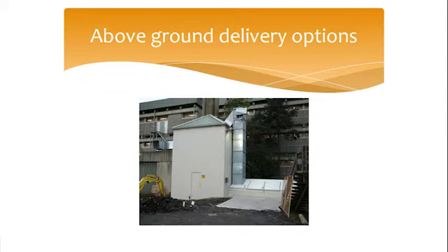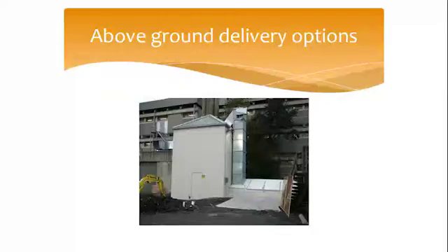This is the University of Otago site, and what's fascinating me now is, now that wood chip is becoming a lot more common in Dunedin anyway, people are starting to have a bit of fun with it. What they're trying to do here is take heat out of their boiler house, and that is an air ducted system, and in the four corners of their boiler house they're dropping the air down. Is this right, Mark? Yep. And letting it come up, so they're preheating, drying their wood chip.